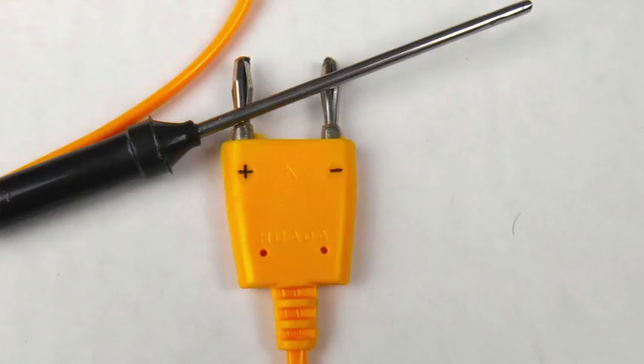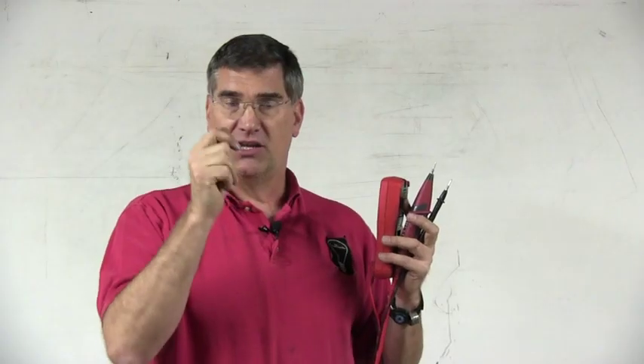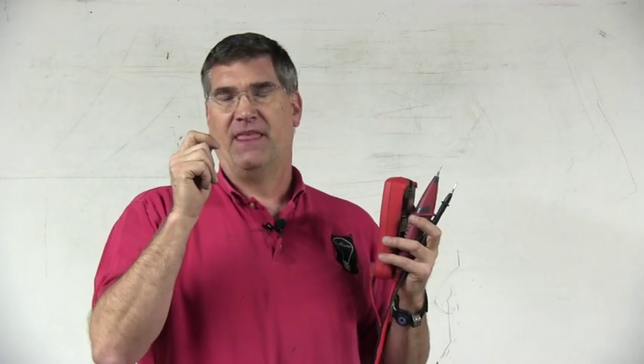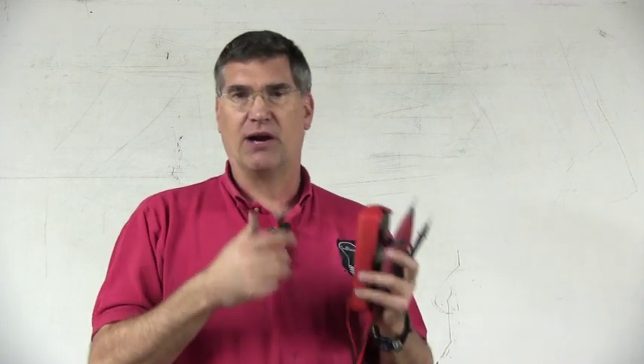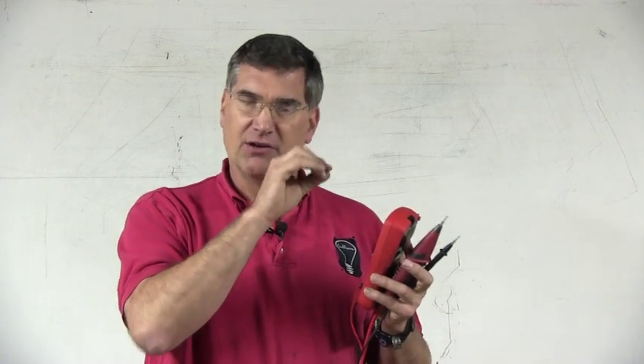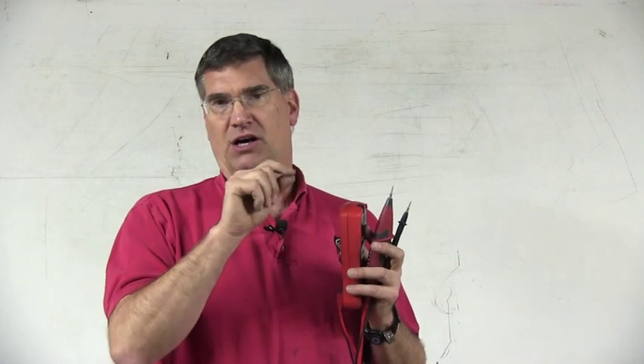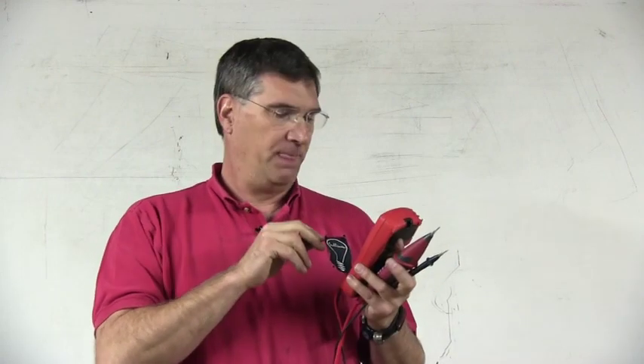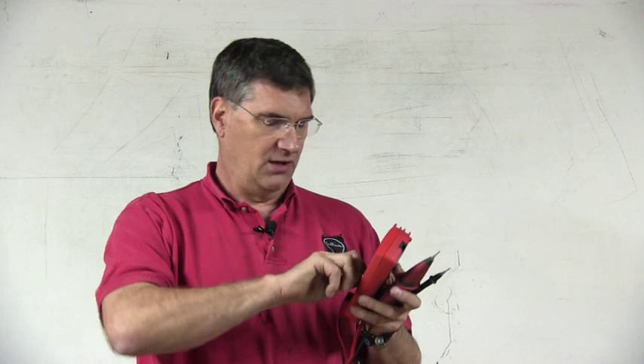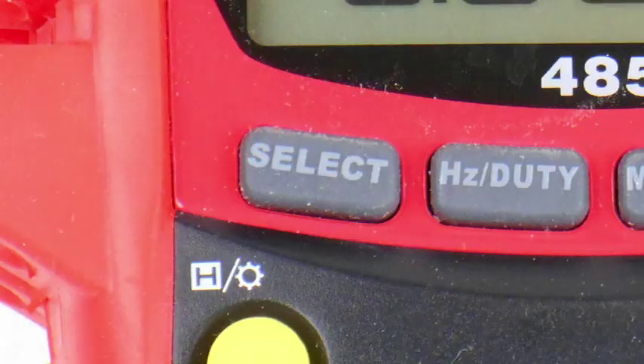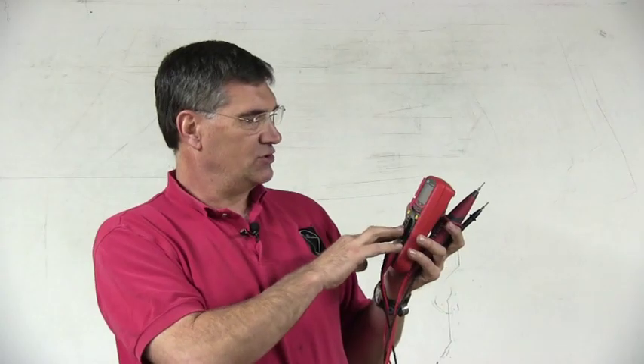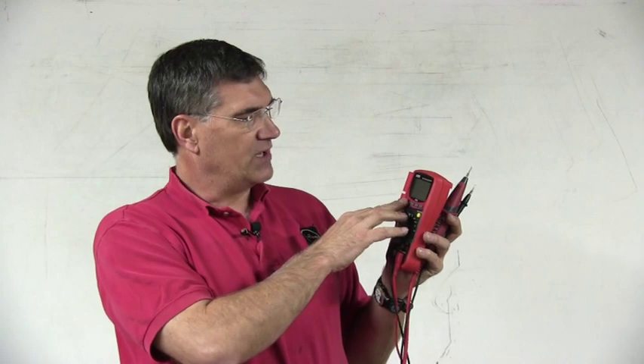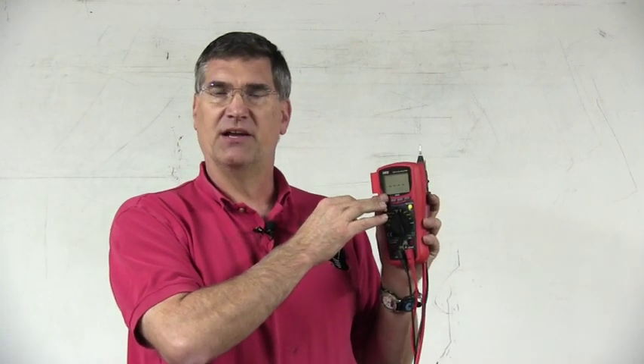So you have to make sure that the plug polarity, the yellow temperature probe plug, there is a polarity. Make sure that that polarity is noted and you insert it into the meter in the proper way. A little hard to see, but there's a plus and a minus that will indicate where you're supposed to connect it. To move between centigrade and Fahrenheit, you're using the select switch again. The select switch is a very important switch on the meter. So you simply choose temperature and then flip between Fahrenheit and centigrade using the select button.